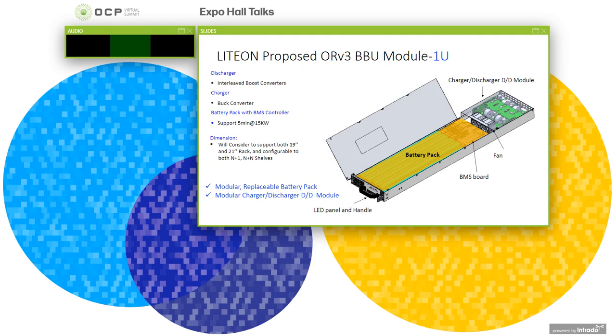So for BBU module design, we proposed a couple of options. The first option is the 1U BBU module, with battery pack and BMS control board, and a charger module with a fan in between, designed for 3 to 5 minutes at full power. We also plan to support a 19-inch and a 21-inch rack, as well as reconfigurable N+1 and N+N shelves. Mechanically, the design will also allow for replaceable battery packs for easy assembly and service.